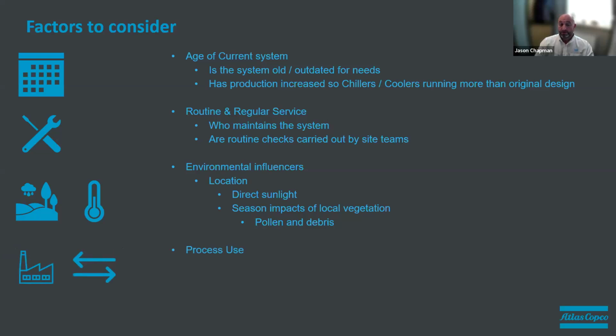Very similar to the compressor side of things, does all the system or all the process require the same cooling needs? Highly likely not. But are we then being inefficient by trying to cool it down to the most extreme of cooling, rather than having a specific point of use chiller for that process, especially if it's only a small part of the production itself? As I say, can point of use chillers be used?